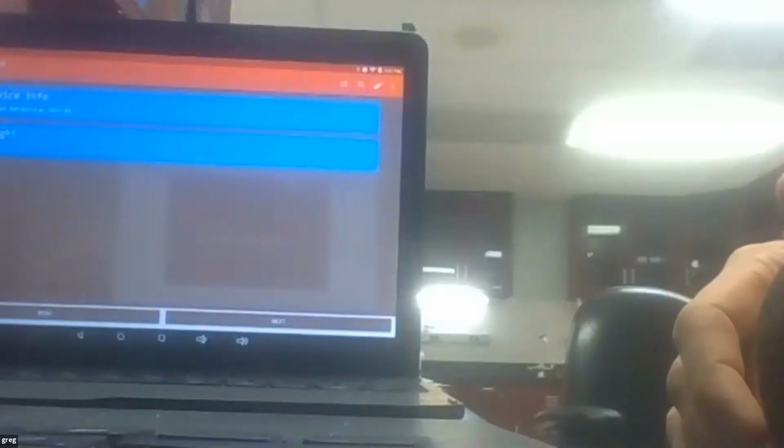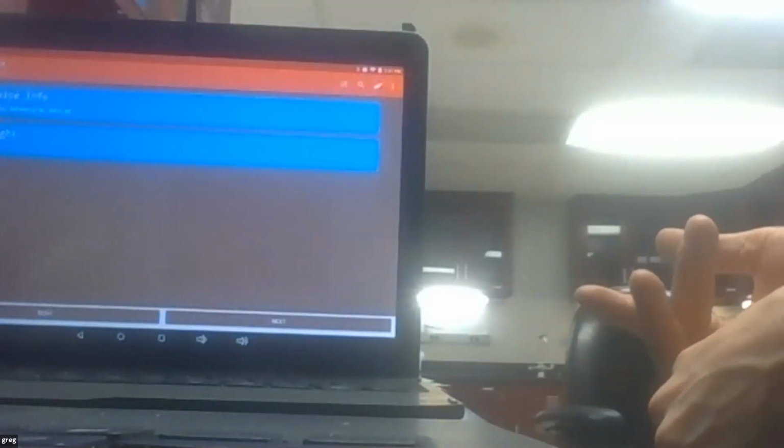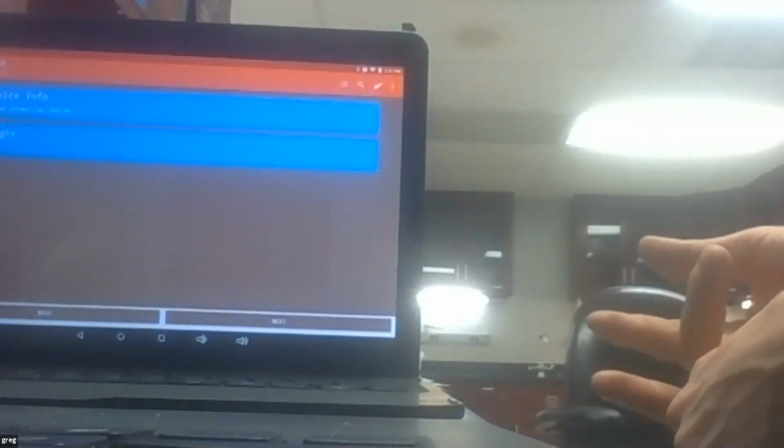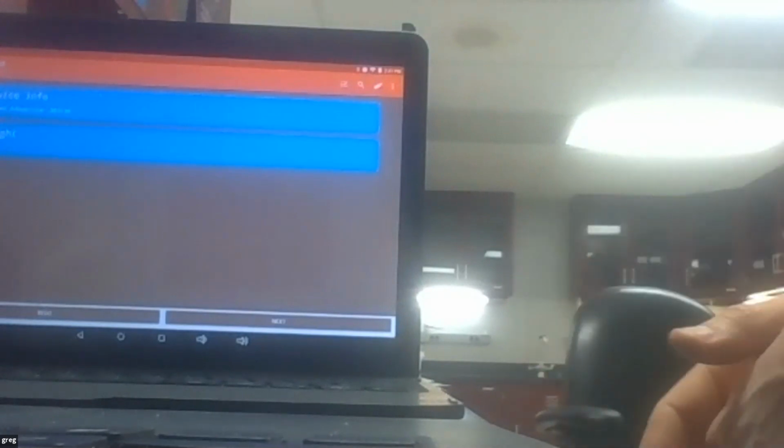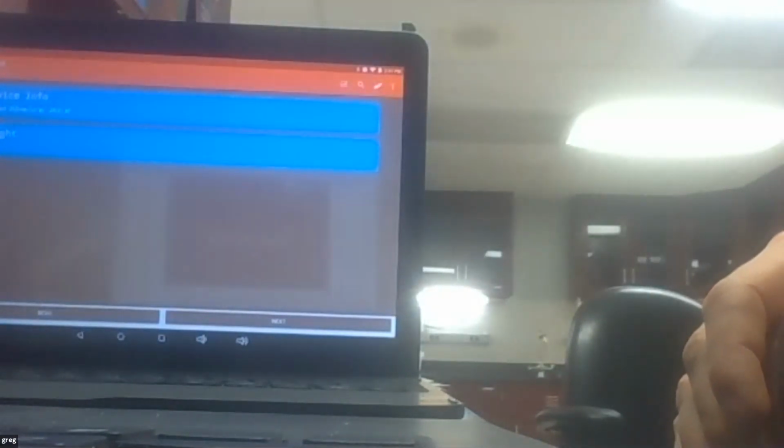So it tells us what it is. It tells us the weight. As long as it's a scale that has a USB out or an RS-232 out, we can absolutely connect to it. That's what those are designed to do. And of course, you can take that information, and because you're writing just a script, you can connect it with information previous. So maybe you had a wet weight from before and a dry weight, and then you wanted to calculate the difference. You could just do that in the script, and you could output it to the user in real time. And if something was out of whack, like the answer was 1,000 and it should have been 1, you could tell them, hey, you probably screwed something up, go back and fix it.